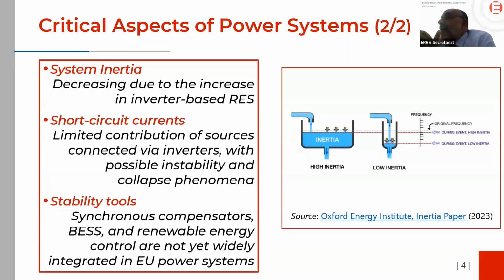Inertia is decreasing because the generation units connected to the network are no longer directly connected like old conventional generation, but through so-called inverters, as in photovoltaics and wind. Unless there is specific regulation named grid forming, which is still very innovative, this kind of generation doesn't procure inertia to the system. Only conventional generation so far procures inertia, although synthetic inertia from wind and solar can be procured, but this is a very innovative process.